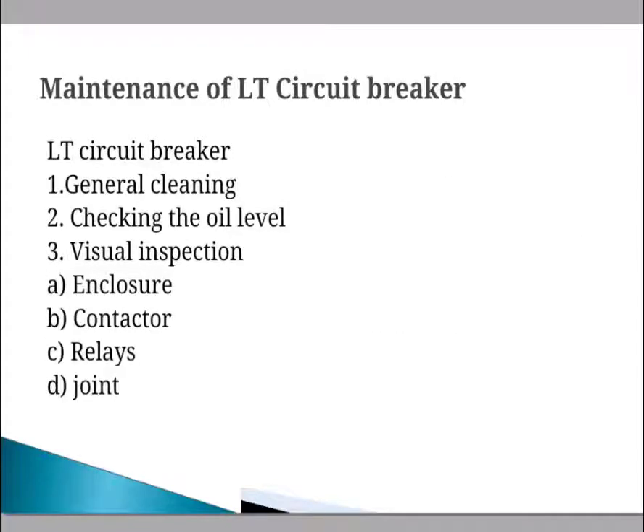For the LT (low tension/low voltage) circuit breaker, we have to check the general cleaning of the circuit breaker and check the oil level. If low, find the reason and add oil. Then perform a visual inspection of the enclosure, contactors, relay, and joints of the circuit breaker.